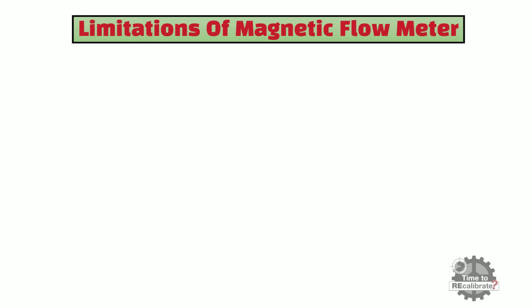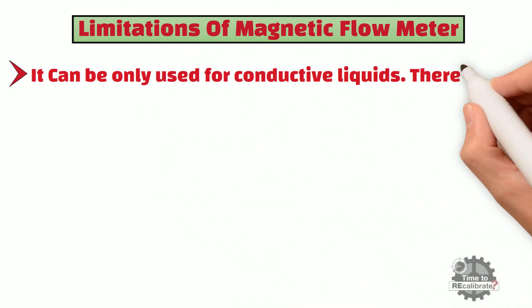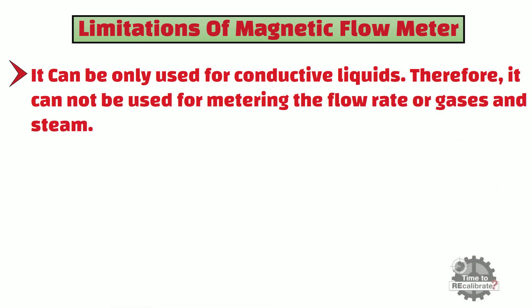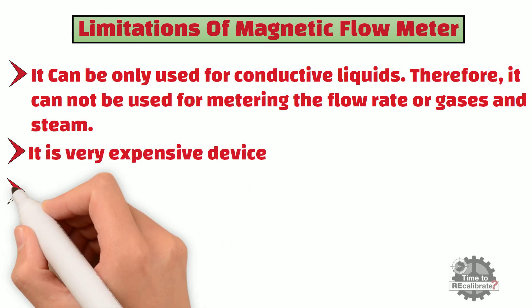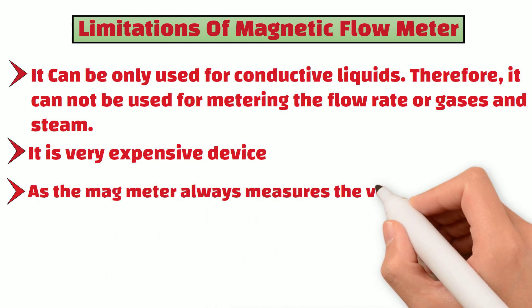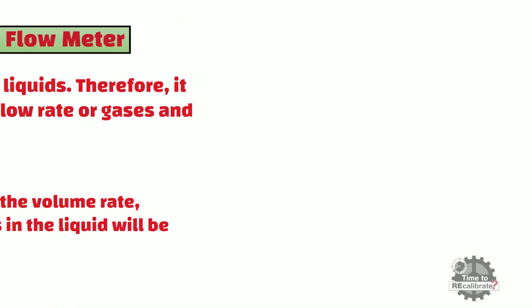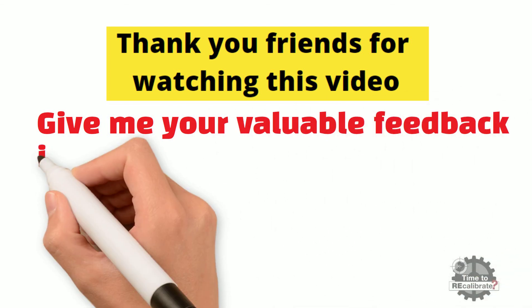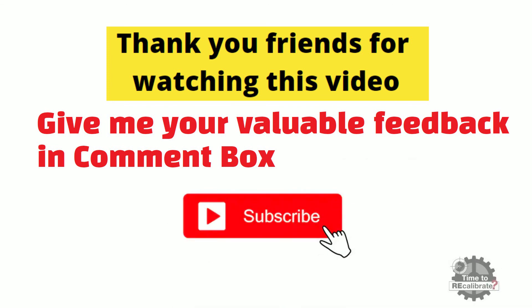Limitations of electromagnetic flowmeters: they can only be used for conductive liquids and therefore cannot be used for metering the flow rate of gases or steam. They are also a very expensive device. Additionally, since the magnetic meter always measures volume rate, the volume of any suspended solids in the liquid will be included in the measurement. Thank you friends for watching — please give your valuable feedback in the comment box, and subscribe so you don't miss future videos.